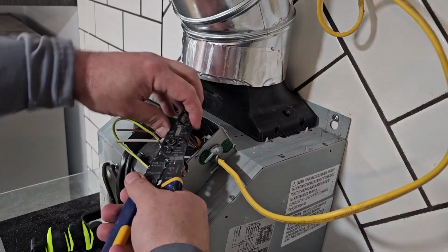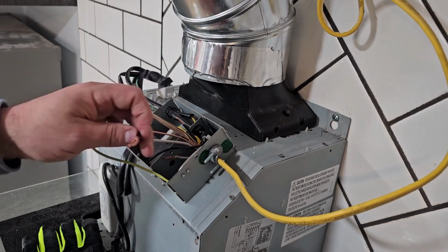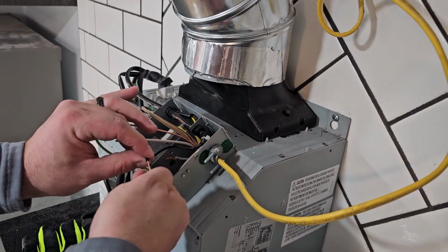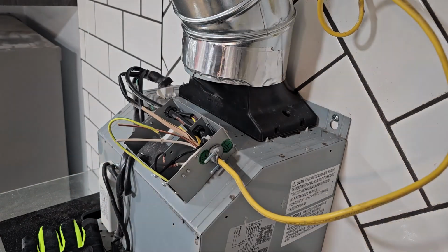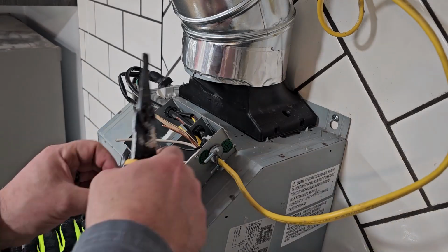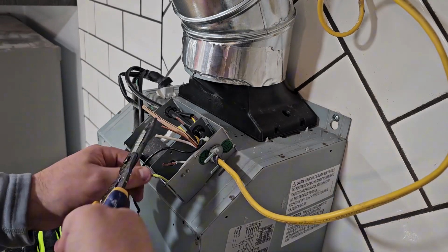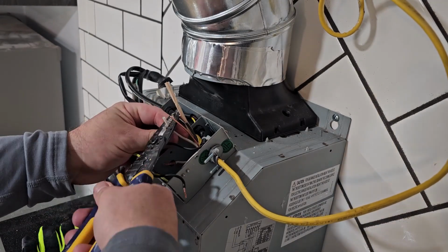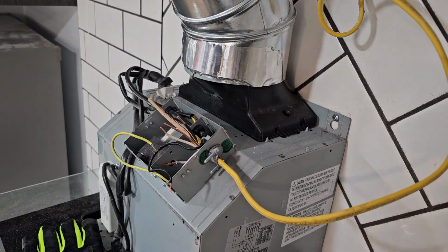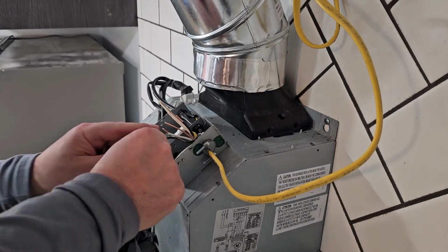Now for my connections, I'm going to be using Wago 221 lever nuts versus standard wire nuts, mainly because I think they hold better and they're just easier to work with. So when I strip the sheathing back, I want to make sure I strip back less than the length of the lever nut, or around a half inch.